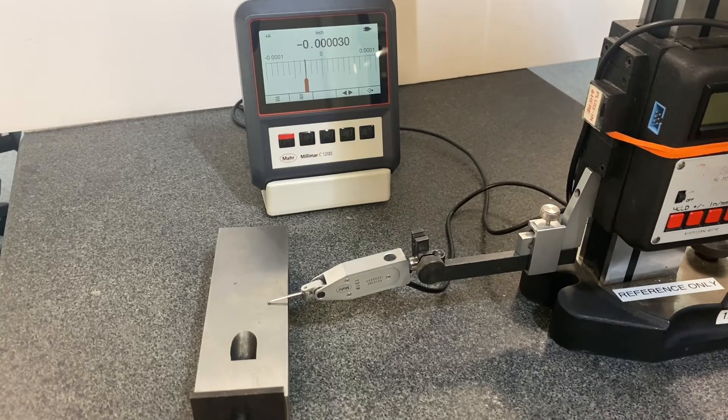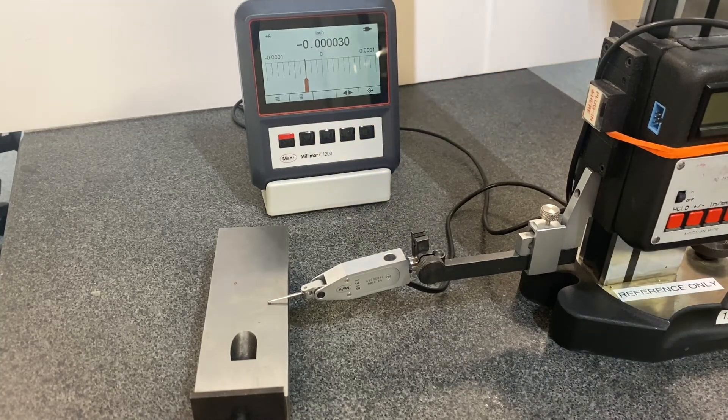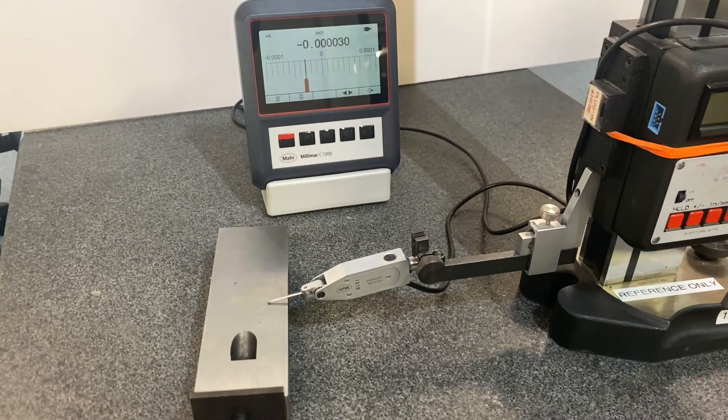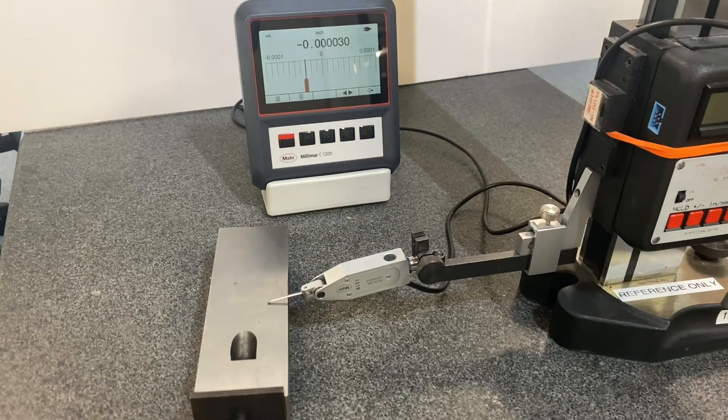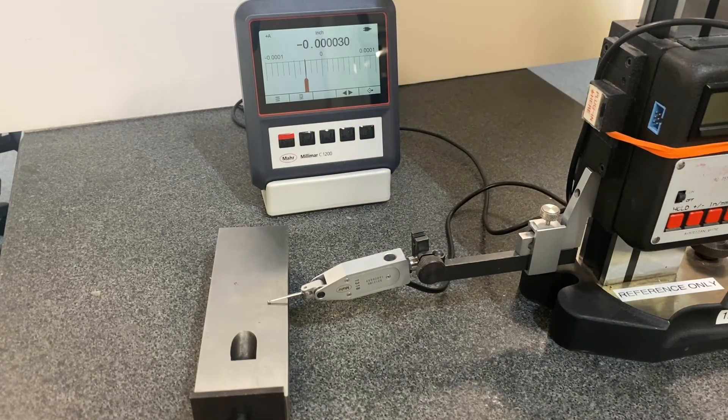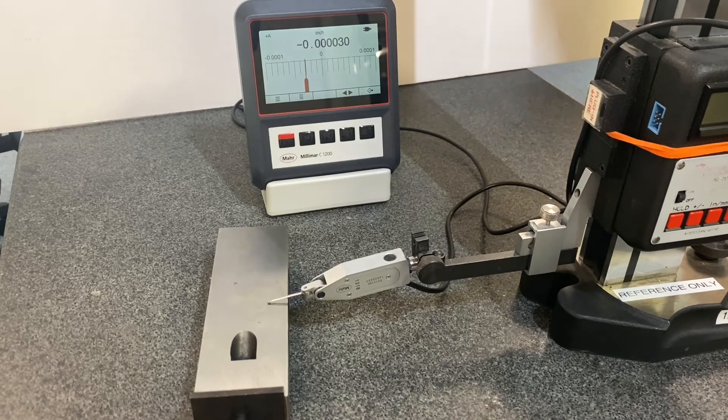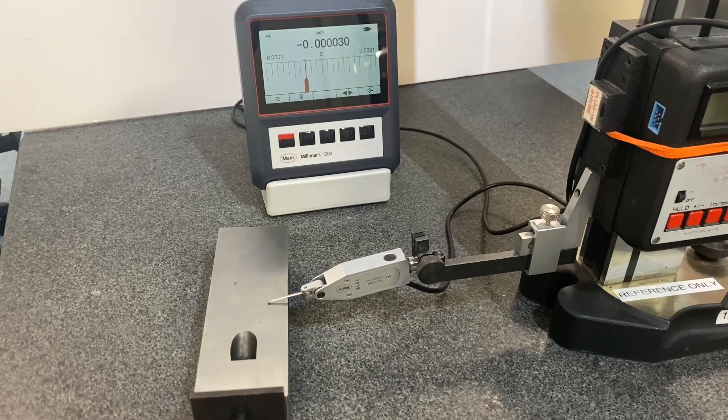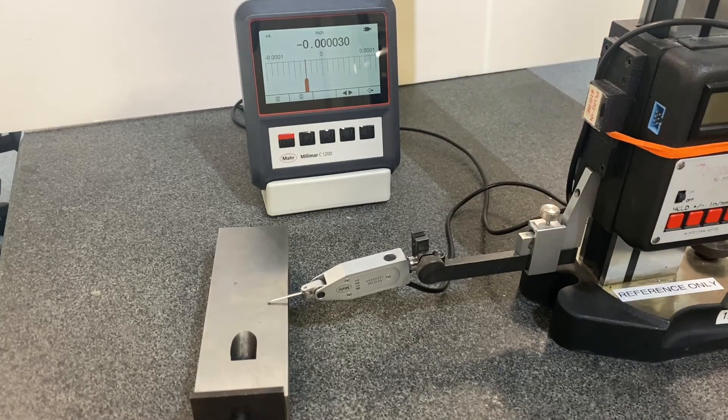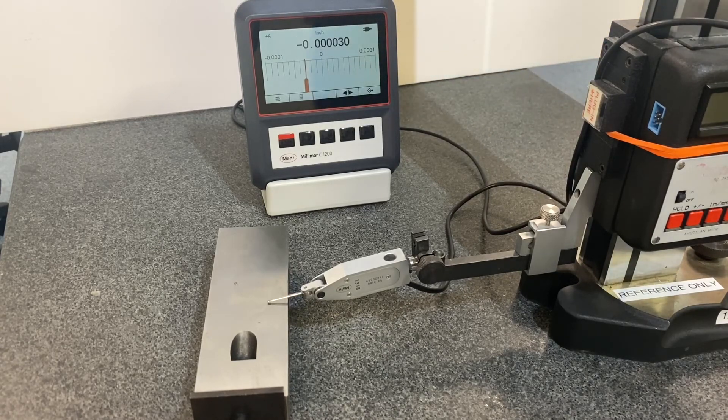So we get a low of 30 and a high of 30 on this side, and I would repeat on the other side as well. Move the probe all over the surface to find the highest and lowest points.